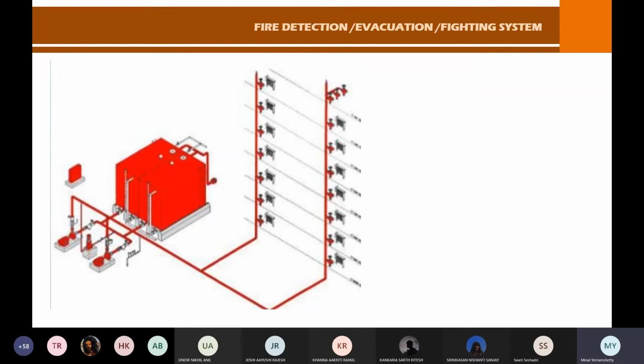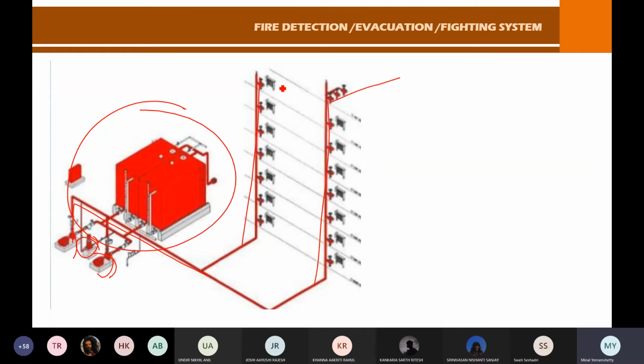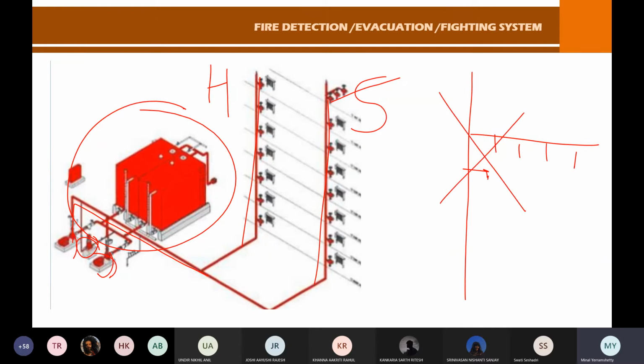Same principle applies. You have a tank here with all the sets of pumps, booster pump and standbys. The risers will come out - one is for the sprinkler, one is for the hydrant. They cannot be the same riser together. It cannot happen that one sprinkler riser is given, and below I put a hydrant but above the sprinkler line is going - this is wrong. You can never do this, as can be clearly seen in the diagram on the left hand side. So this is what you'll have to show in your drawings, in the sense, in your case study.